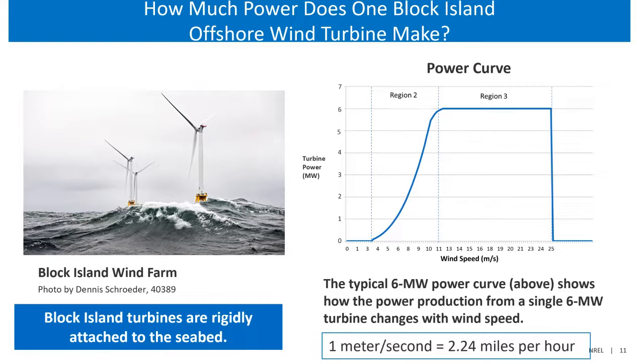Cutout happens, in this case, at 25 meters per second, a little over 50 miles per hour, and then it just shuts down. The way it shuts down is the blades feather - they call it feathering. The blades feather, and there's no longer any torque on the rotor, so the machine shuts down. One of the reasons why wind turbines are so safe is that any one of the 3 blades can feather itself and stop the machine. So we have triple redundancy on all the machines out there, and that's an important safety feature that prevents machines from running away in high winds.